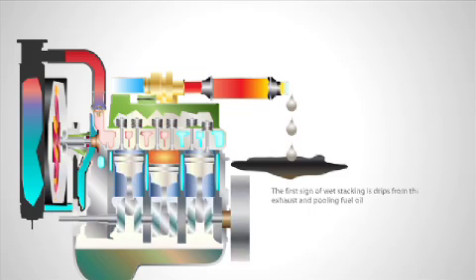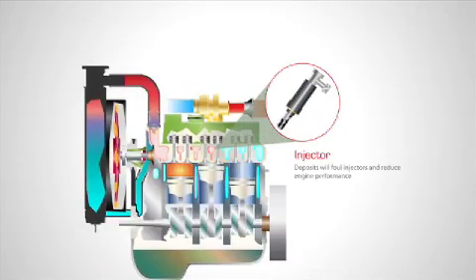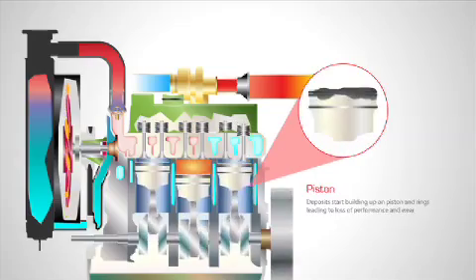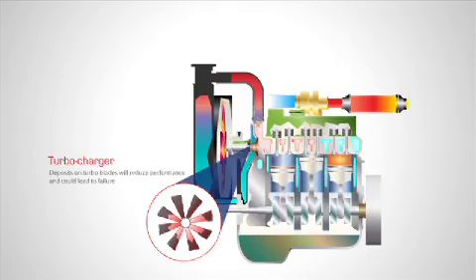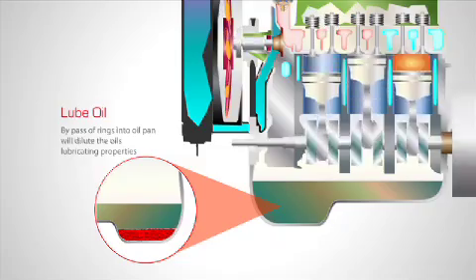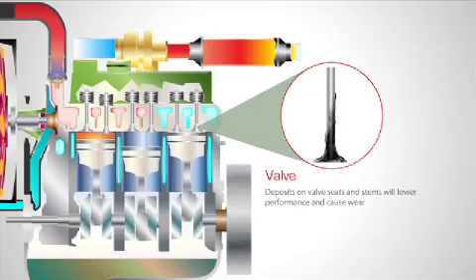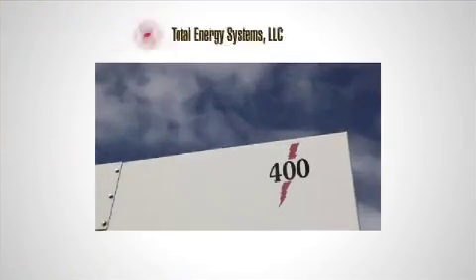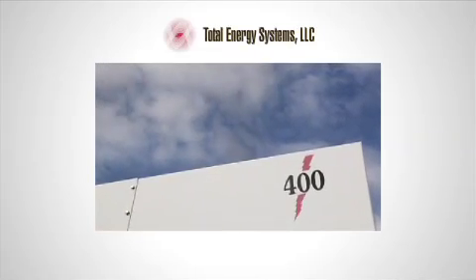A generator that is continually run on a light load will start to exhibit the symptoms of wet stacking. Carbon deposits will form on injectors, pistons, rings, turbochargers, valves, and accumulate in the lubrication oil. All of these conditions will result in reduced performance and reduced engine life. Removing carbon deposits from key internal components increases maintenance time. A frequent sign of an engine suffering from wet stacking is excessive black smoke on startup.